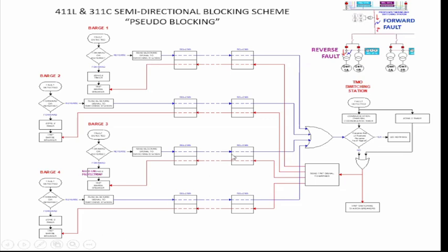The point here is, if there's a fault at the barges, the healthy barges will contribute fault current, and this allows the faulted barge to isolate so it will not cause cascading. Imagine 42 generators, 242 megawatts, that if not properly coordinated will trip, and it will really have an impact on the grid. It's actually a loss of generation. So what is the impact on the distribution system if you lose a source? Your load becomes larger compared with the generation, which will cause under frequency. That's why Meralco's automatic load dropping may operate. Imagine 242 megawatts. So we need to ensure the selectivity of the protection. That's the impact.